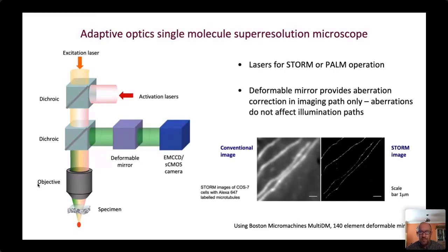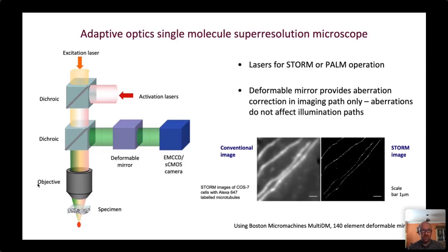Aberrations affect this microscope by blurring the point spread function of each molecule's image. When we run the fitting routines — fitting emitted light to a known model of the microscope's point spread function — there are errors due to the discrepancy between the aberrated and ideal point spread functions. The consequence is that the fitting routine fails in some cases and we lose some data; in others where fitting succeeds, the precision is lower, resulting in a lower quality final image.